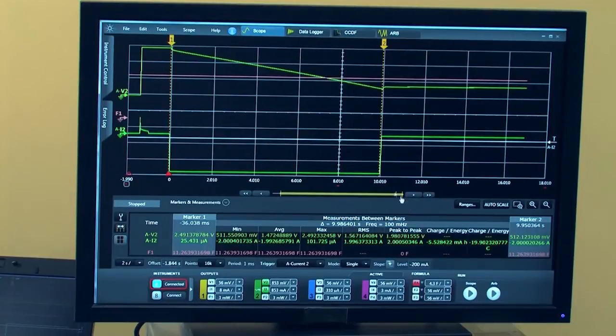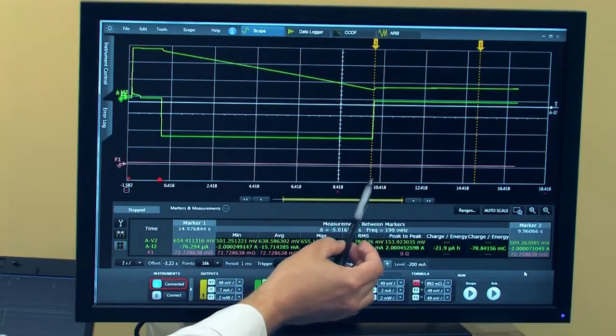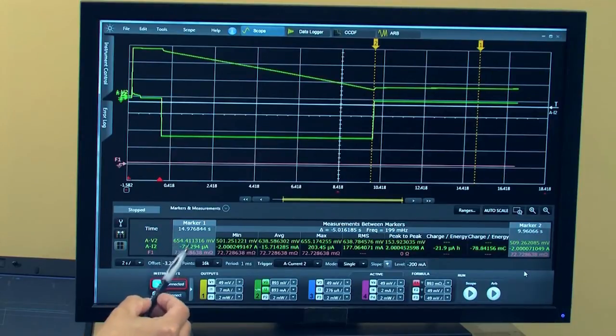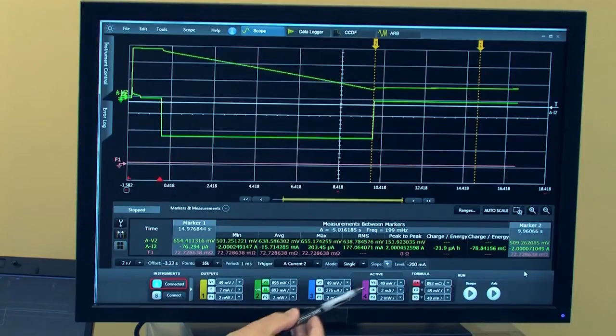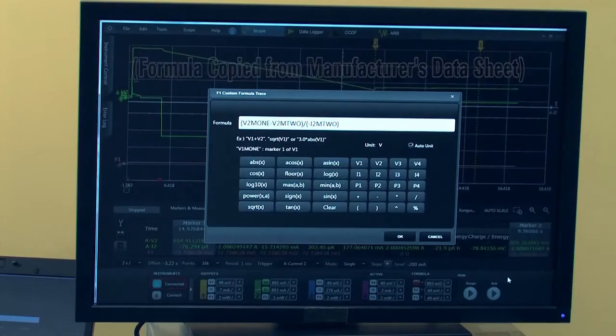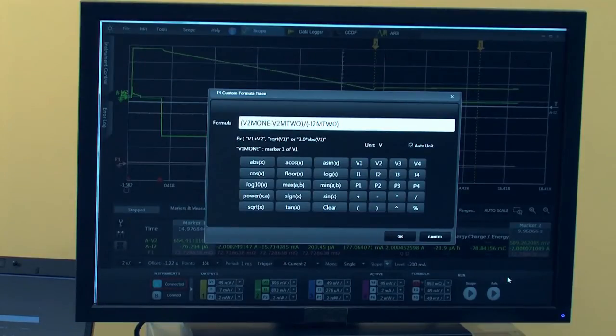The next measurement we're going to be doing is ESR measurement. I'm going to load my profile again. The markers are placed in specific locations as per the formula. You can manually calculate based on marker data, but we are now offering a custom formula that I will be showing you — where you can enter the actual custom formula and be able to calculate the ESR of this device.